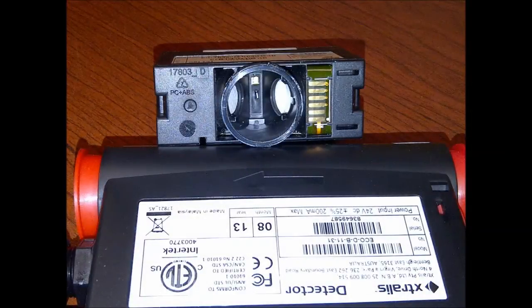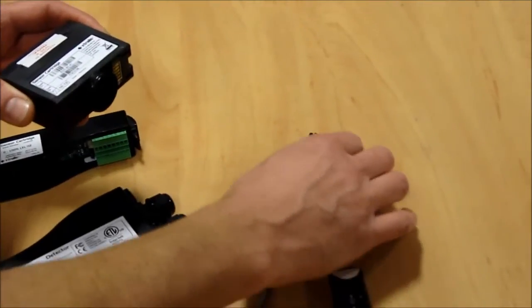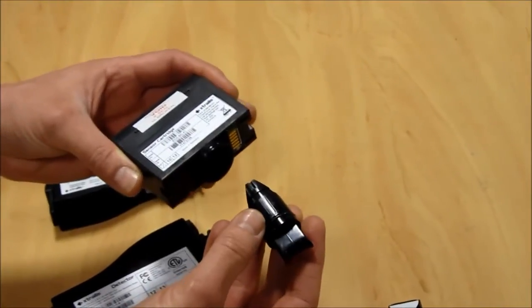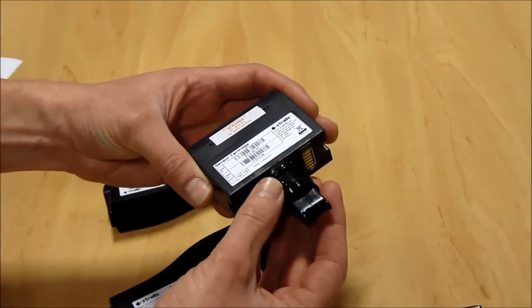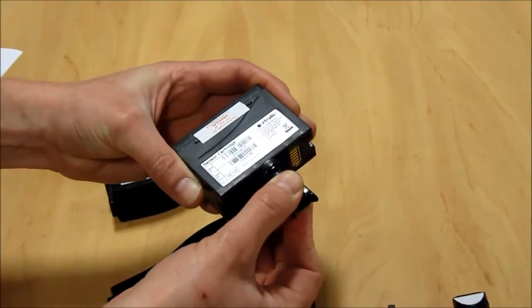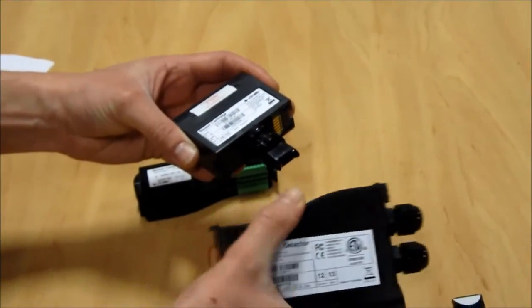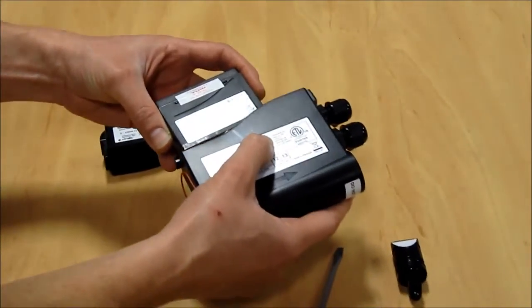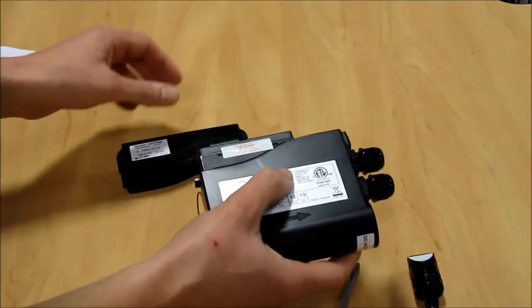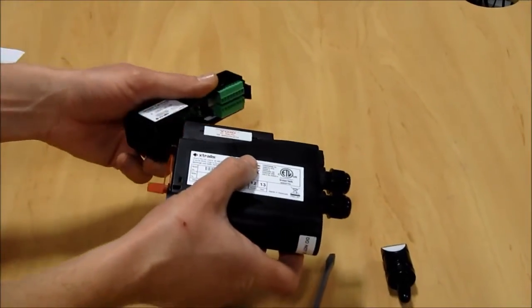Confirm that the flow sensor, the small tab in the center, still sticks straight up and has not been bent. Gently adjust if needed. Now, fit the new filter assembly in the cartridge. It is keyed to go in only one way, and it snaps in place. Reinstall the sensor cartridge in the eco body and replace the lid.